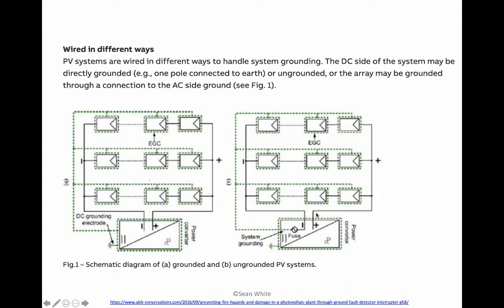Another thing that's a little bit different is when we would put fuses in a combiner, which we don't see right here, but when there were fuses in a combiner, in the 2017 and after versions of the NEC, we only need to put fuses on one polarity. Earlier, we would put fuses on both polarities on this formerly known as ungrounded inverter, and we would put fuses on a single polarity on the formerly known as grounded inverter. There's a few different things. Now what we do is we do the same thing for both of these inverters. So we disconnect positive and negative. We put fuses on a single polarity, and we can use USE-2 wire or PV wire.